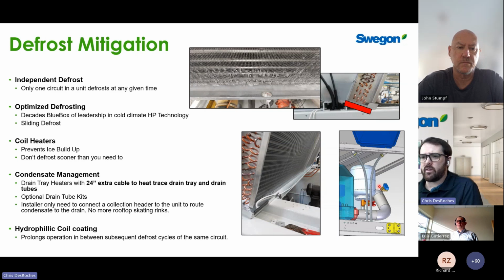And one of the other key features too is we've opted to go with a standard hydrophilic coating coil. So we typically see this on VRF type systems where you might have a blue coating. This is actually a coating that attracts water, because after we finish a defrost cycle, if we have any water droplets left on the fins and we start the compressors again, we're going to freeze that immediately. And if that happens, we're going to start accumulating ice much quicker. And now we need to defrost prematurely than what we should need to if that ice wasn't forming there right after defrost. So in our labs, Chris?